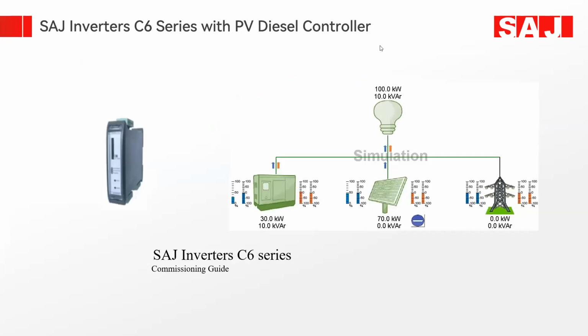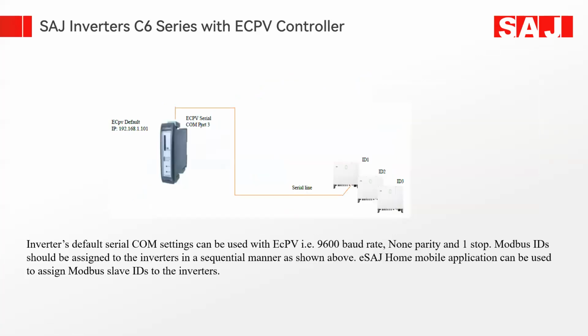SAJ inverter C6 with the PV diesel controllers. In the EN Combi, we have a commissioning guide for the installers and EPC companies on how you can configure C6 inverters with the PV diesel third-party controllers. Inverter default serial COM settings can be used with ECPV: 9600 baud rate, no parity, and one stop bit. Modbus IDs should be assigned to the inverters in a sequential manner as shown above. The eSAJ Home mobile application can be used to assign Modbus slave IDs to the inverters.